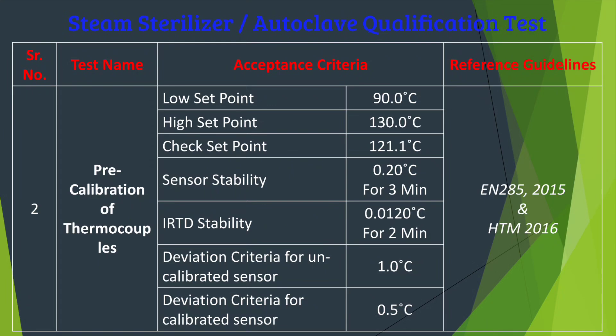The deviation criteria for an uncalibrated sensor is 1°C, and for a calibrated sensor is 0.5°C. There are no specific set points given in guidelines; these are taken from various sources. General guidance in EN 285:2015 and HTM 2016 states that thermocouples used for temperature mapping of steam sterilizers must be calibrated. These parameters are used in recent practice for pre-calibration and post-verification of thermocouples.